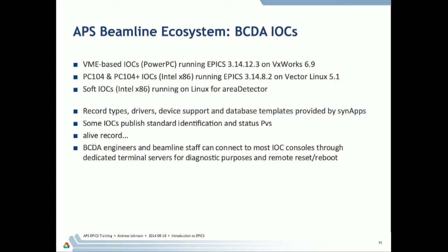On the beamlines, and really I'm only talking about BCDA systems here, a lot of those are VME-based IOCs again, PowerPCs running VxWorks. There are also some things called the EPICS Brick, which is a PC104 or PC104 Plus system running on Vector Linux, and we have IOCs running there, and also soft IOCs. Mainly, those are used for area detector taking images from detectors. All the record types, device support, and database templates are provided by synApps. So Tim Mooney's software and BCDA group putting that collection together.